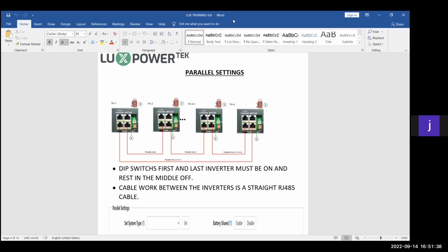Okay, I see there's a question. What these 2 dip switches are basically doing is adding a resistance to that specific line, and that's how the inverters know which inverter is where. So if you switch your 2 dip switches up, then the inverter knows this specific unit and this specific unit are the first and the last unit in the communication chain. That's the only function that these 2 dip switch boxes have.